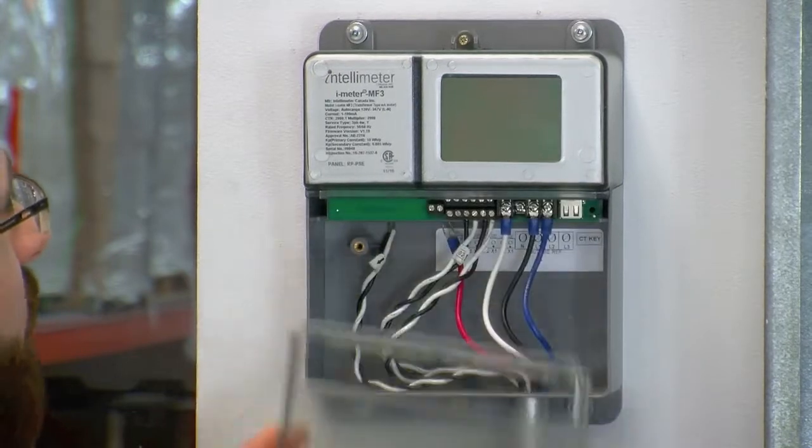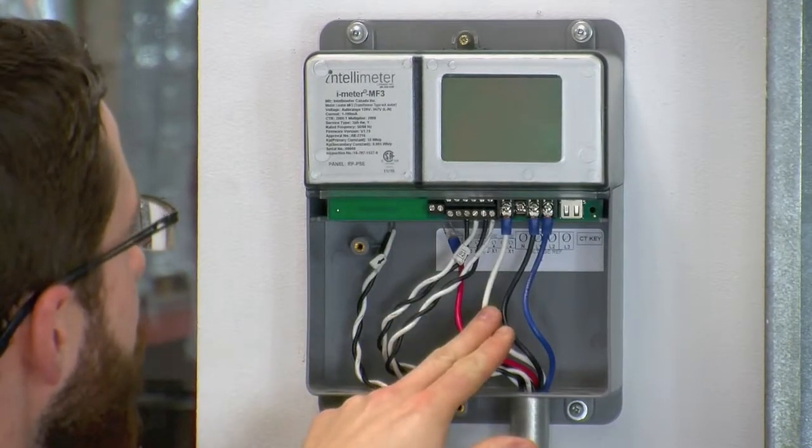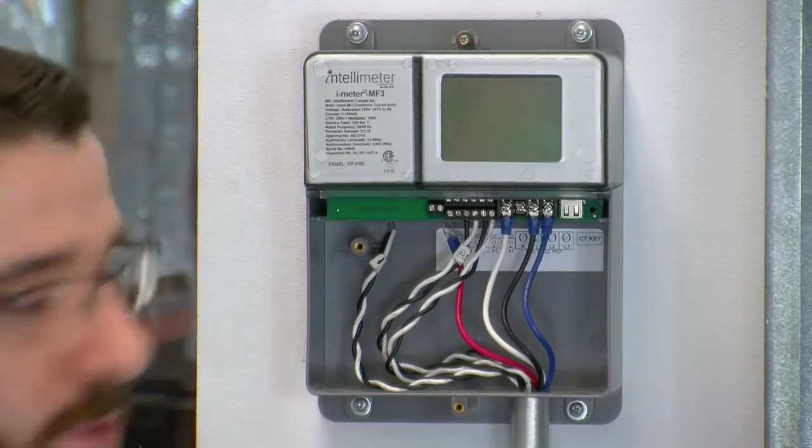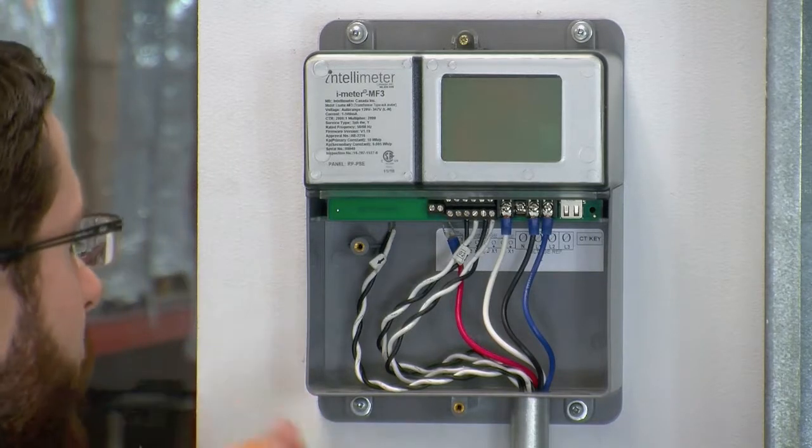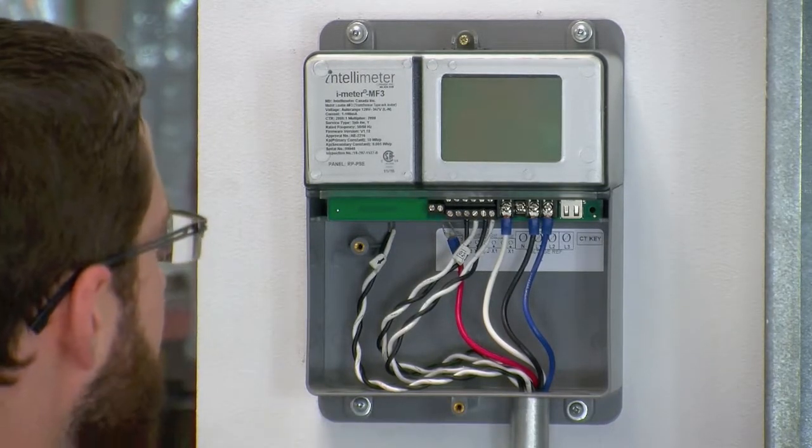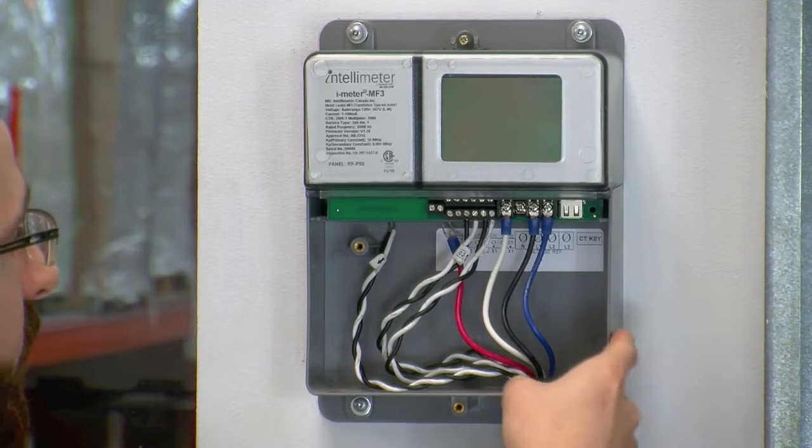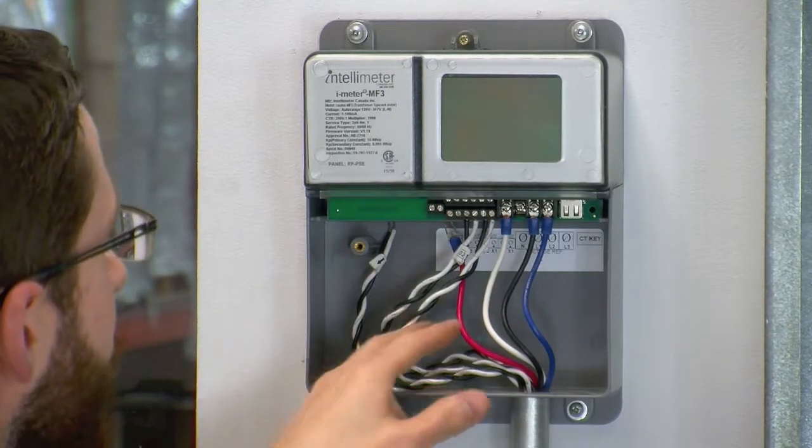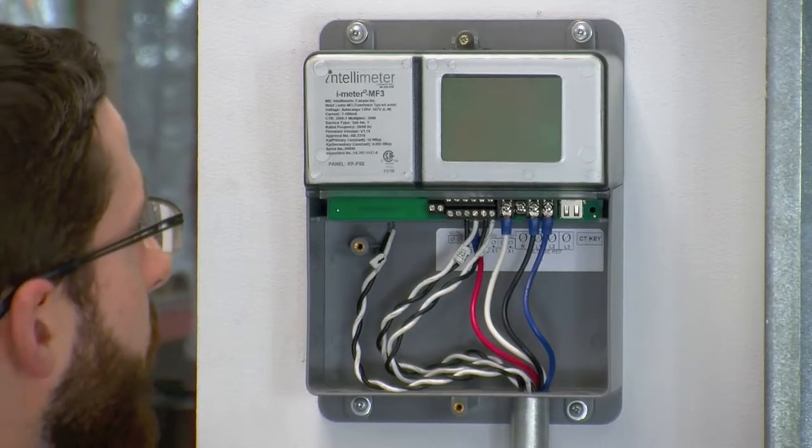As you can see, we now have our CT leads and reference voltage wires pulled through the conduit into the enclosure. For the sake of this demonstration video, we've only pulled them through the one piece of conduit, but personally, I would suggest adding a second piece of conduit so that you can keep your CT leads and reference voltage wires separate. But for now, we're just going to use the one.